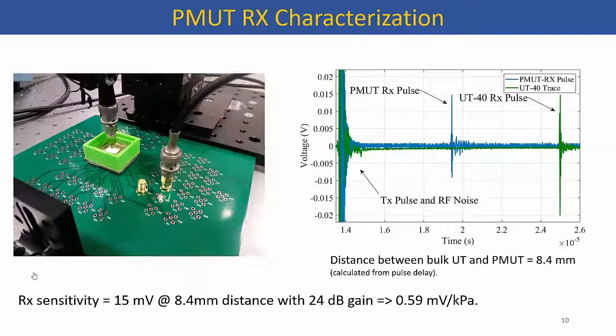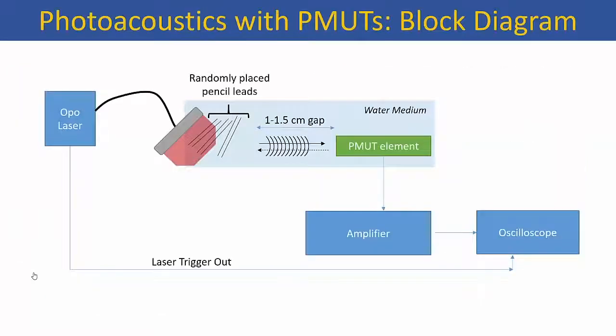For basic characterization, without going into details about LDV or impedance measurements, we were interested in underwater operation. So we used a bulk ultrasound transducer, threw sound from the top, and verified that the PMUT can listen to the sound — confirming it works in principle. We also estimated the received sensitivity by knowing the pressure generated by the bulk transducer as measured by a hydrophone, and combining that with the voltage received. The received sensitivity came out to around half a millivolt per kilopascal, which is very low. So there is a lot of scope for improvement in these transducers, and we have achieved that as I will show later.